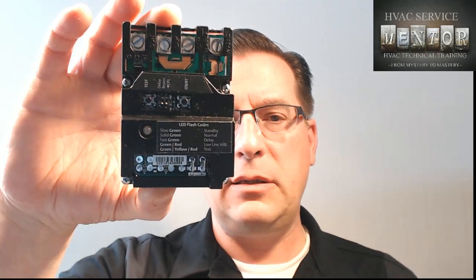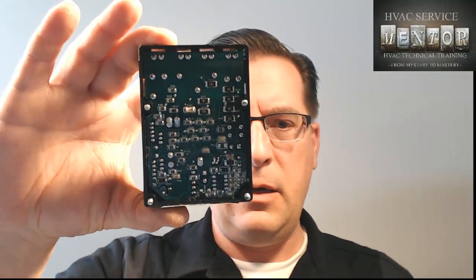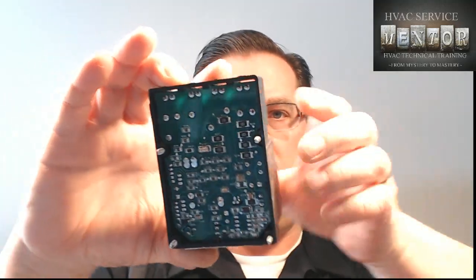This, as you can tell, has an electronic circuit board built into it. Here's the back side. There it is. You might think, what in the heck is this thing? This is pretty unusual. This is a contactor. This does the exact same thing that a conventional contactor in an air conditioner or heat pump outdoor unit does, right? On demand, it closes a set of contacts, which energizes a compressor and a condensing fan motor.